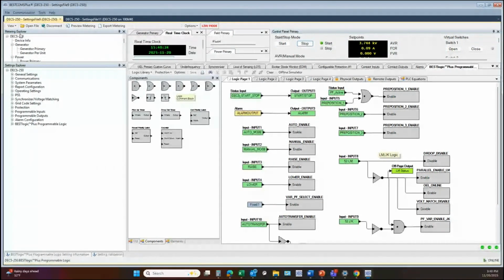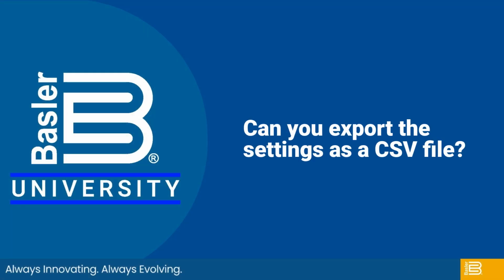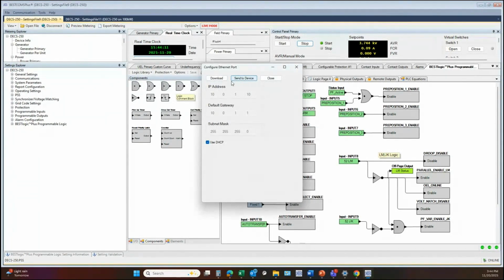But if you want to save it as a PDF, it would be that print option that I had mentioned, where you would go through that to save it as a PDF. Can you export the settings to a CSV or XLSX file? Export to file. That's where you would set that to a CSV file. If you need to change the Ethernet settings, it's found up under communication and then configure and then Ethernet. This is where you define or disable the DHCP and then define the IP address, gateway, and subnet. That's again communication at the top, configure, and then Ethernet.